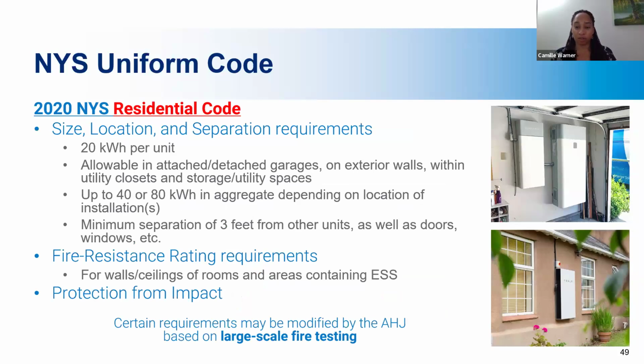So this is the residential code. It goes over the size, location, and separation requirements for BESS systems, and these are your small systems. Each unit must be 20 kilowatt hours or less. If it will be inside of a garage, it may have up to 40 kilowatt hours. If the system will be placed outside, it can be up to 80 kilowatt hours as long as there is a 3 feet separation from other units.